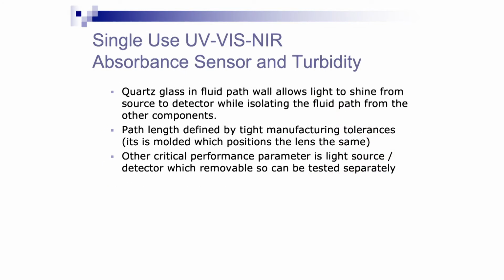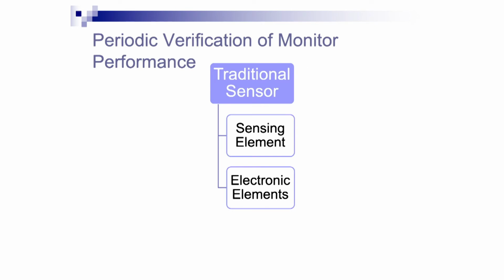For conductivity, the temperature sensor undergoes the same process as just described, and each one of these conductivity sensors is tested with a range of buffers up to 100 millisiemens, and the optimal K is determined, it's printed on the tag, and the user enters that K factor. So each one has its own unique individual calibration. As far as the absorbance sensor, again, it's really control of the path length and making sure the quartz glass has not been contaminated during the manufacturing process to make sure it still has its full clarity. And there's a separate method to test the monitor itself.